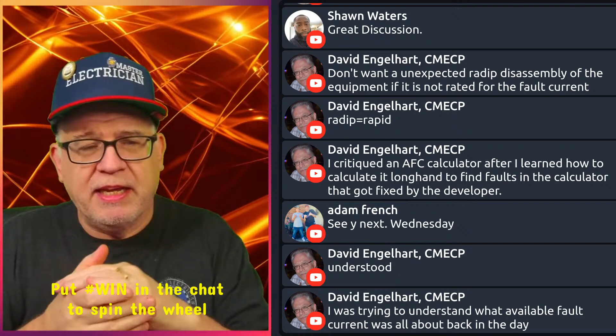If I have a piece of equipment with an SCCR rating and an AIC rating that is equal to or greater than the service source or actual source available fault current, due to the length and impedance, it's impossible for that to have an available fault current downstream that exceeds that at the source. It's kind of like selective coordination: if it's selectively coordinated at the breaker here, and the one below it is exactly the same, then it does not have to be selectively coordinated because it's exactly the same. You know what I'm saying?